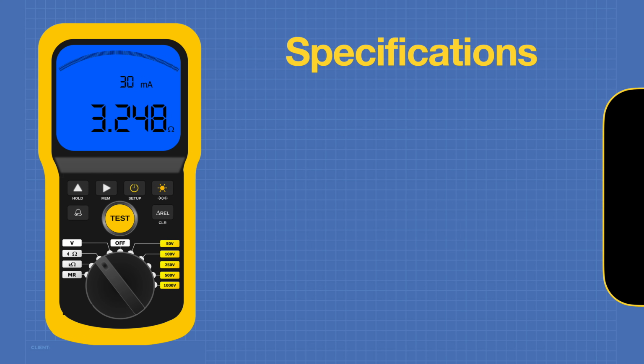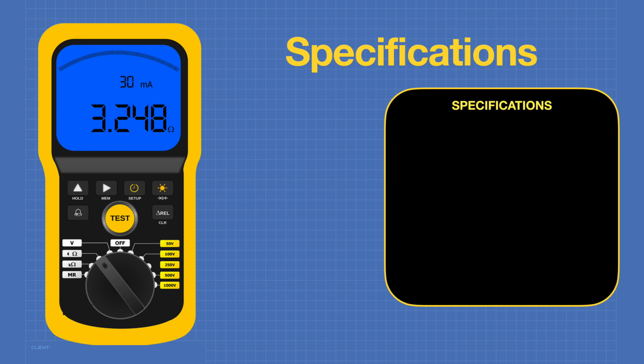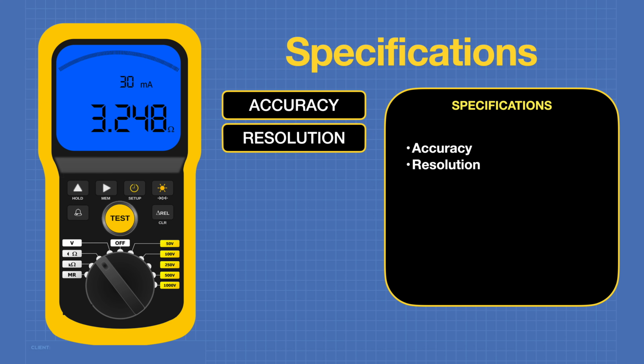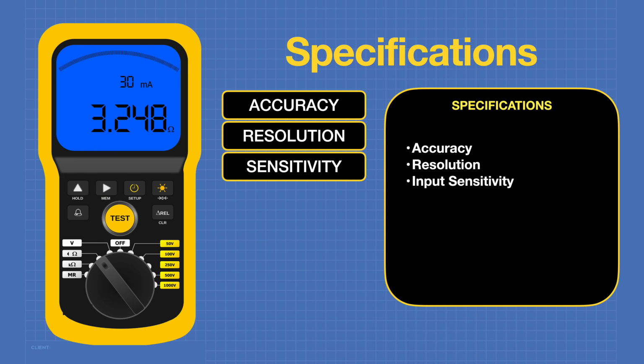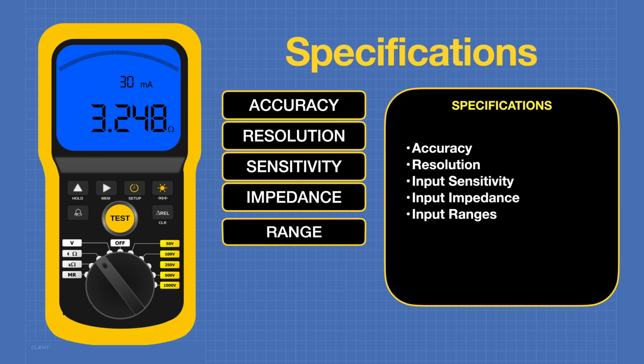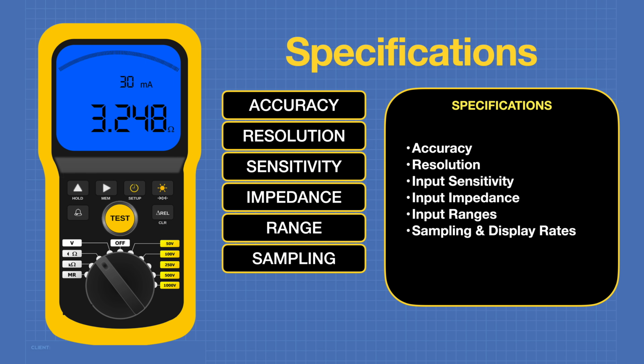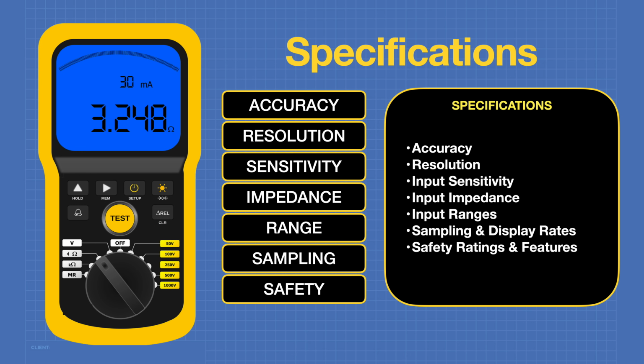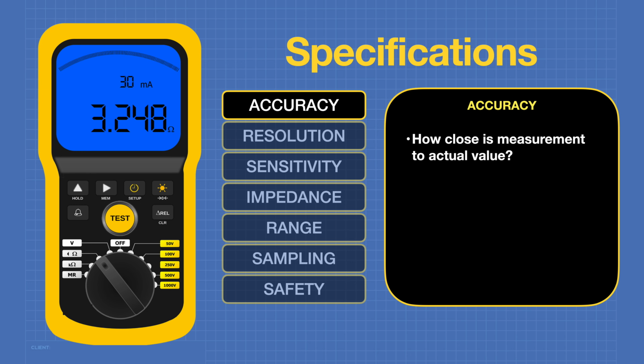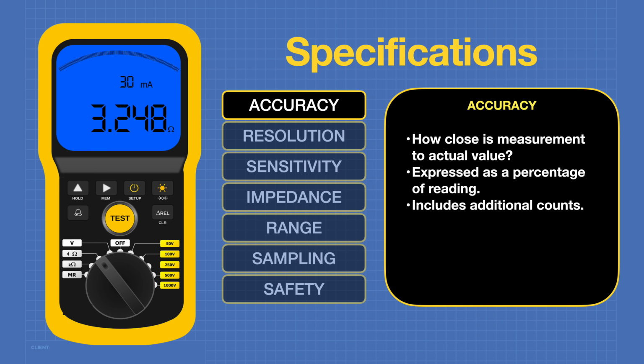A good multimeter will come with a very long list of specifications, and you can break those down into the following categories: accuracy, resolution, input sensitivity, input impedance, the input ranges, sampling and display rates, and safety ratings and features. Accuracy defines how close a measurement is to its actual value. It's expressed as a percentage of the reading. An accuracy measurement also includes additional counts. You'll find accuracy listed for each function on the multimeter.